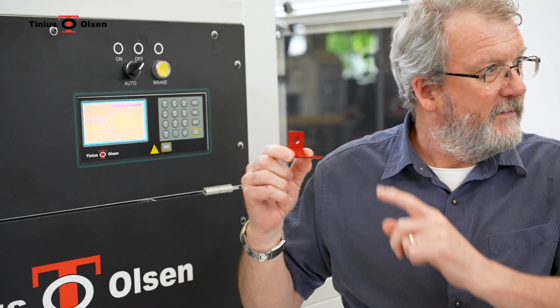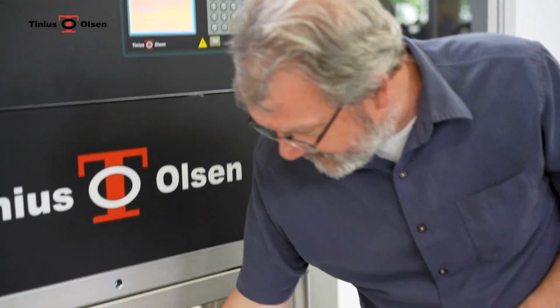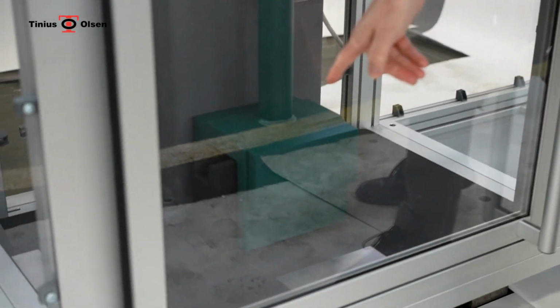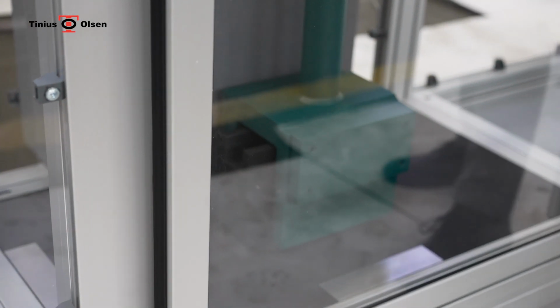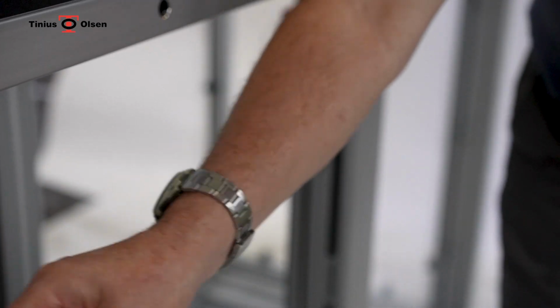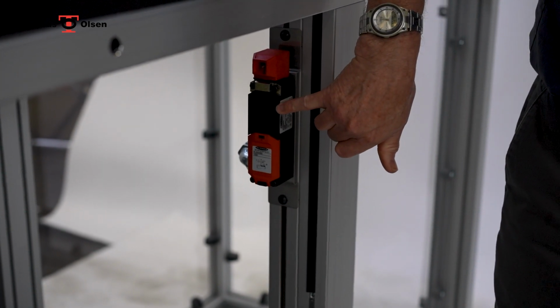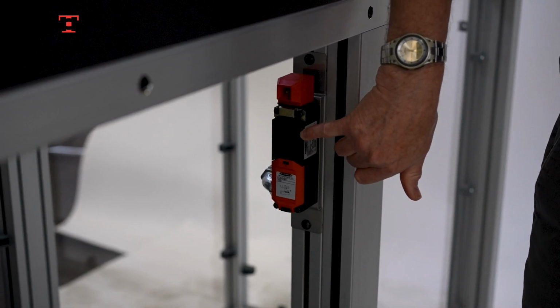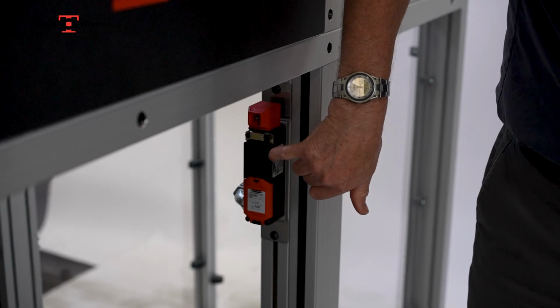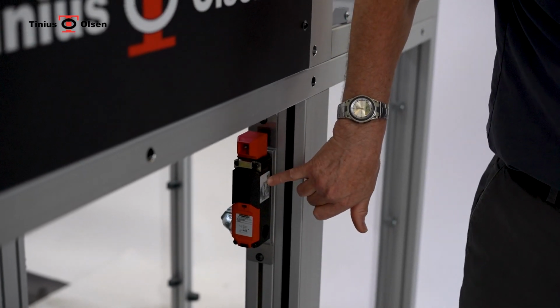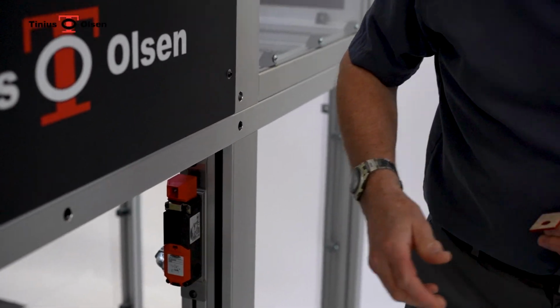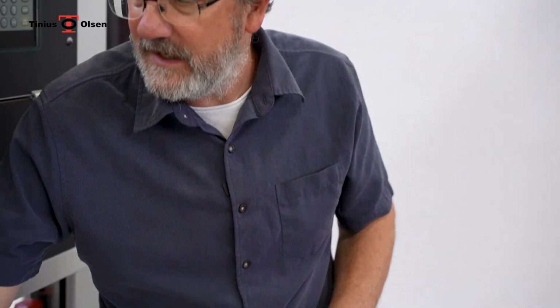We need to remove a shipping bracket, which holds the hammer in place, the anvil bodies, and we will also need to adjust the lock screw on here to the lock position so the door will remain locked when it's supposed to be locked. We ship these unlocked to allow ease of installation. Upon completion of those two tasks, we are ready to perform a calibration on the machine.